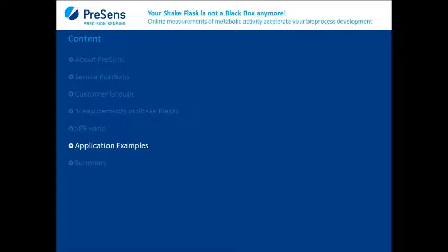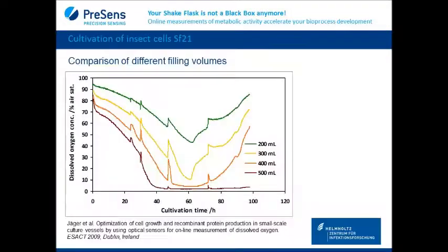Now I'd like to show a few examples of applications of the Shake Flask Reader Vario. So this is an experiment where a 1 liter shake flask was used with various volumes. And what you can see here is the dissolved oxygen concentration in the shake flask at various filling volumes at a constant shaking speed. And you can see that in a 1000 milliliter shake flask at 500 milliliters filling volume, the dissolved oxygen concentration is down after about 40 hours of cultivation time due to the low aeration in the high filling volume. So this shows you clearly that at lower filling volumes you have way better aeration, and you can see this with our system without having to draw a sample. The spikes that you see in the measurement curves are actually reference measurements that were done by drawing samples, and you can see in these spikes that drawing of the samples has a severe impact on the values in your shake flask.